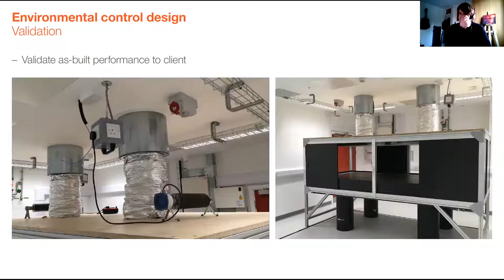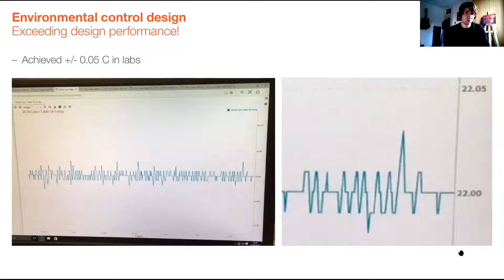Again, that was a real success, and we found during that testing that we were able to achieve the tight temperature control needed. In fact, we did better than the brief - we were able to remain within plus or minus 0.05 of a degree centigrade, so really tight, stable environmental control.